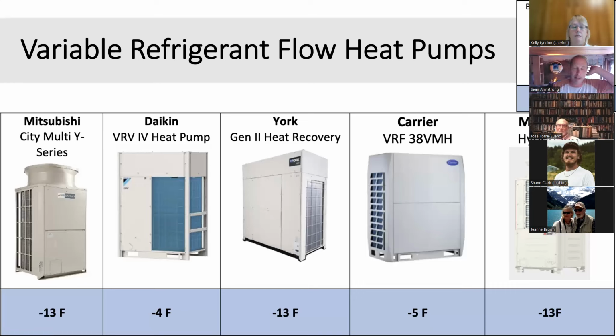VRFs, as they're abbreviated, are popular, and they're expensive. I don't like them personally because there's so much refrigerant involved. What they do is heat and cool refrigerant in that box and release it out, but then it goes to a manifold, which has an alarm and an extra pump system. And from the manifold, it sends out more refrigerant in smaller lines throughout the building. It's just a lot of refrigerant, which has a relatively high global warming potential. And it's expensive to keep sending and stopping it, holding it and pumping it and moving it around. It's just the most expensive way to deliver heating and cooling.